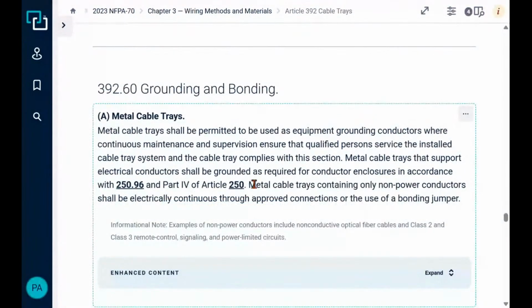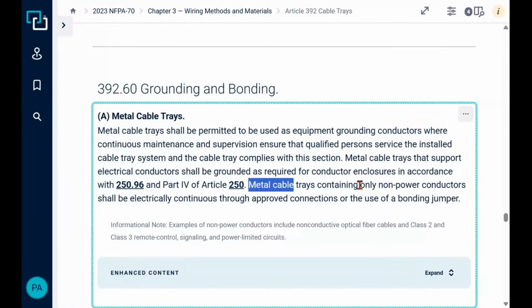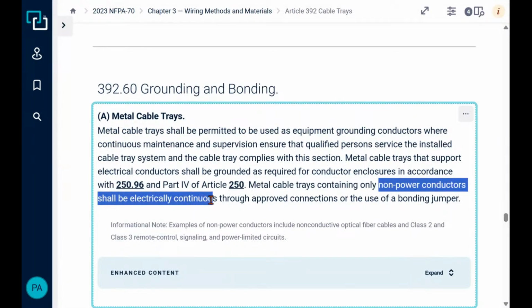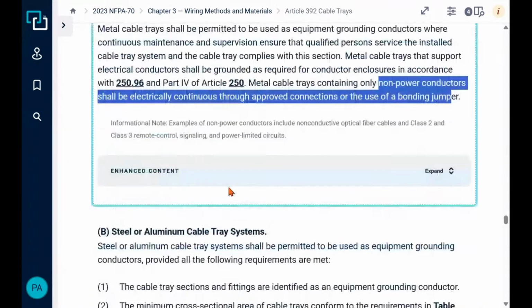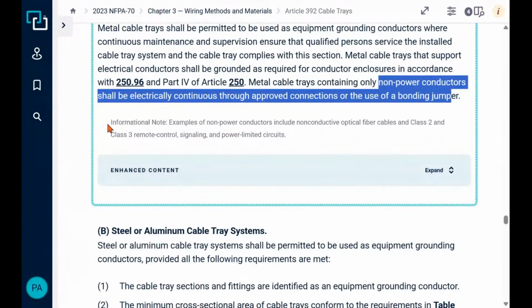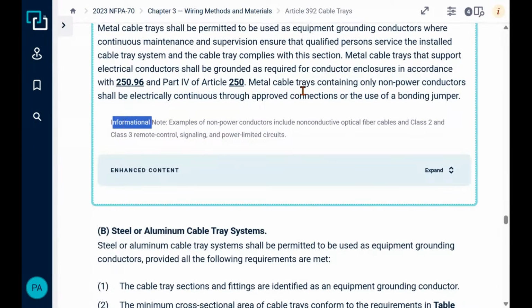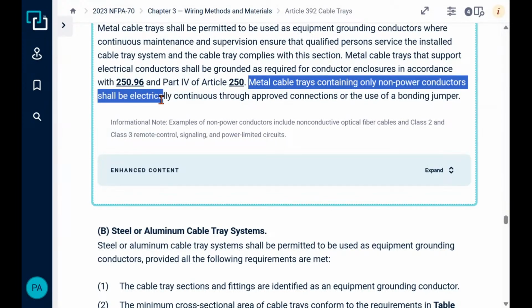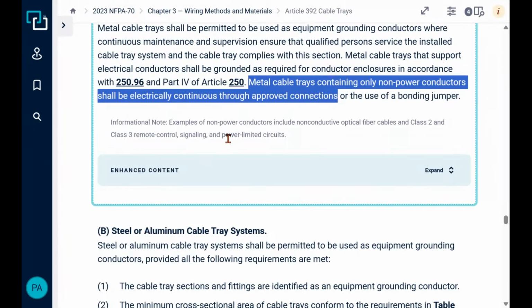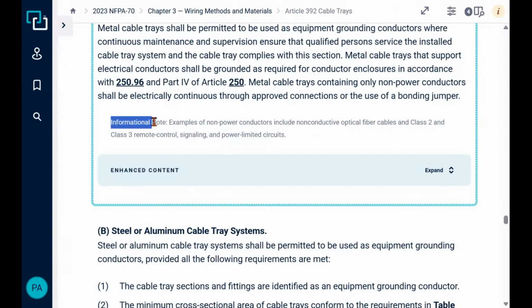Then it goes on and says metal cable trays containing only non-power conductors shall be electrically continuous through approved connections or use of a bonding jumper. So again, we do have an informational note, because people say, well, in this last one, non-power conductors shall be electrically continuous through approved connections. What does it say? So down here you see an informational note. And this is a good reason we have informational notes, because you're saying, well, it should be obvious.